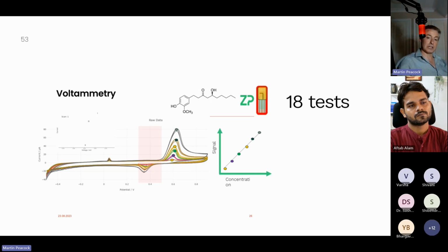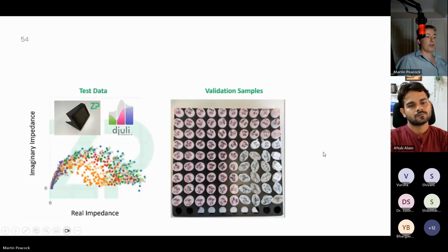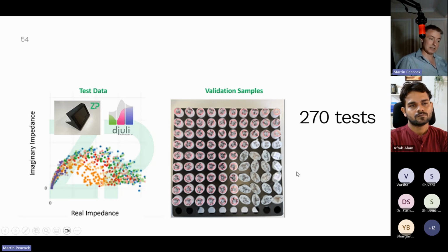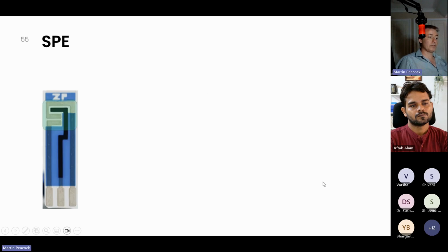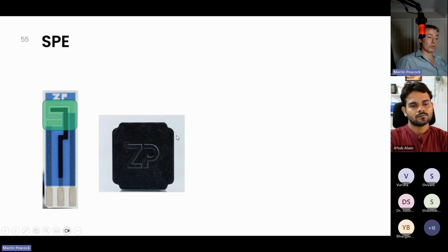And I think single channel potentiostats really don't cover it. This is an example of some work that we did. It was impedance spectroscopy. We did over 270 tests. Now we did that in probably something like a day, but we can't do it unless we're doing parallel testing. So I'm obviously a big fan of using screen printed electrodes. If you're making an IVD device, an in vitro diagnostic device, use small volumes. Don't stick the sensor in the solution. Put the solution on the sensor. That's closer to what the real world product will do.